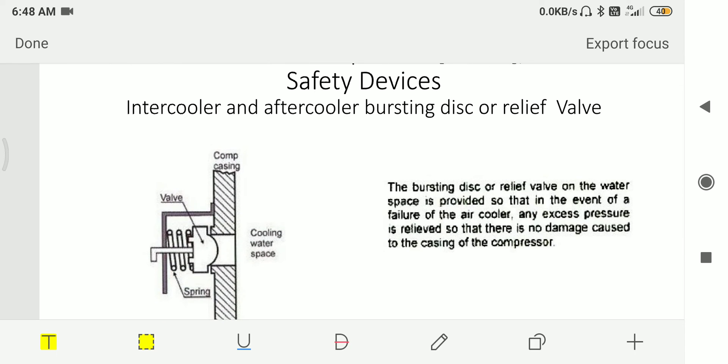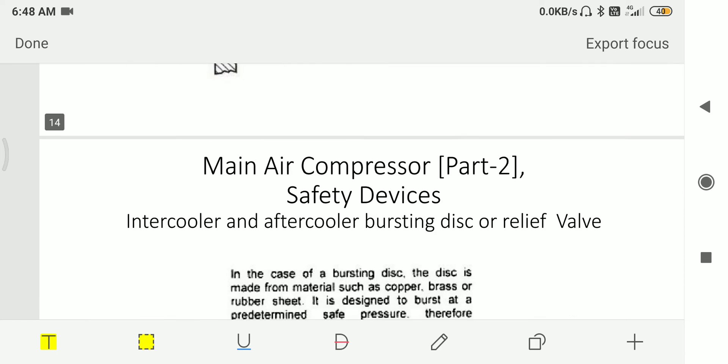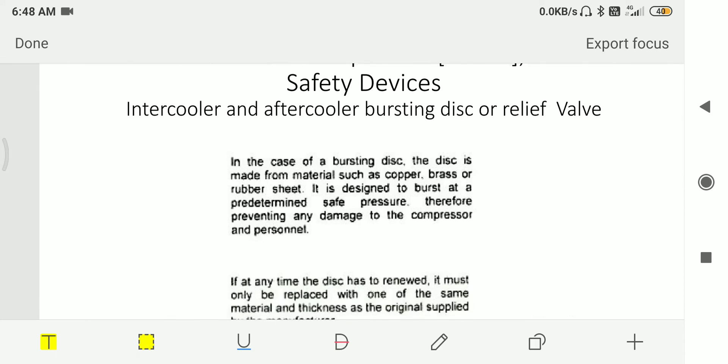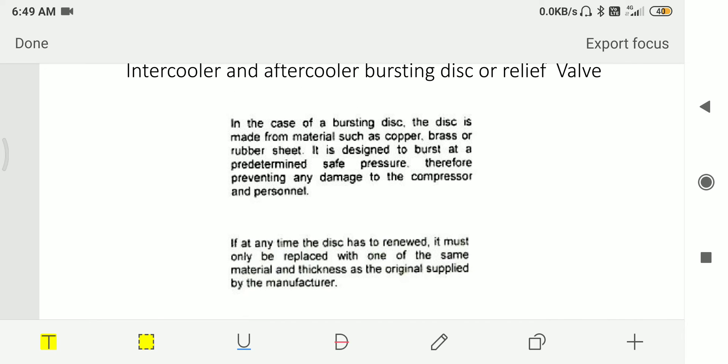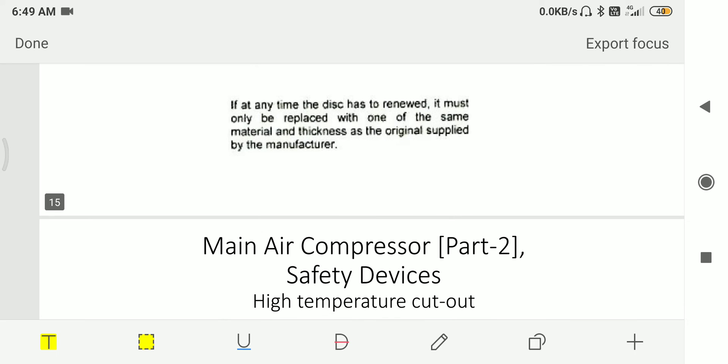Then bursting disc for the intercooler, aftercooler, or relief valve. Bursting disc or relief valve on the water space is provided so that in the event of failure of air cooler, any excess pressure is relieved so that there is no damage caused to the casing of the compressor. In case of bursting disc, the disc is made from materials such as copper, brass, or rubber sheet. It is designed to burst at a predetermined safe pressure, thus preventing any damage to the compressor and personnel. If at any time the disc has to be renewed, it must only be replaced with one of same material and thickness as the original supplied by the manufacturer.